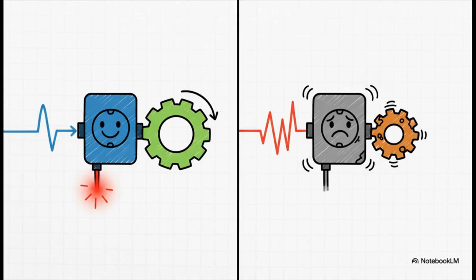That heat leads directly to our next problem: terrible efficiency. Motors don't run as well, and your power factor, which is just a fancy way of saying how efficiently your system is using electricity, it just tanks. This means your whole system has to pull more power from the grid just to do the exact same amount of work.